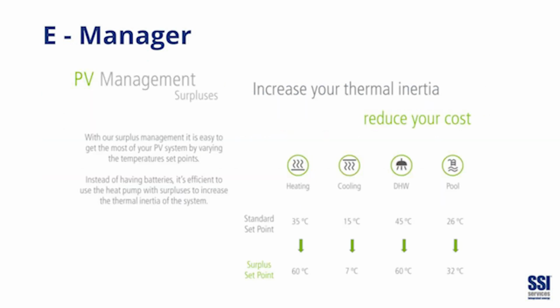This is typically what happens with your standard set point: 35 degrees heating for an underfloor system, and we can ramp it up to 60 degrees. You'd have mixing after the thermal store so you control the temperature. Same with cooling - remember, this works with cooling as well, and cooling is needed when the sun is at its strongest, so there's a real potential saving on costs. That can drop your cooling store temperature from 15 degrees to 7 degrees, so it's a fair amount of energy you're storing there. Same with domestic hot water, and if you're lucky enough to have a swimming pool, you can do it with that too - nice swimming at 32 degrees.